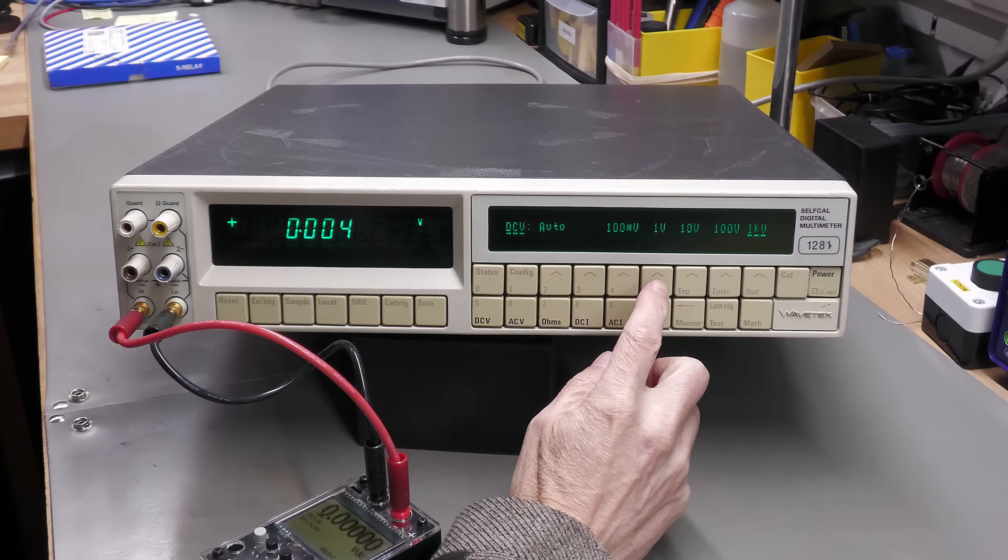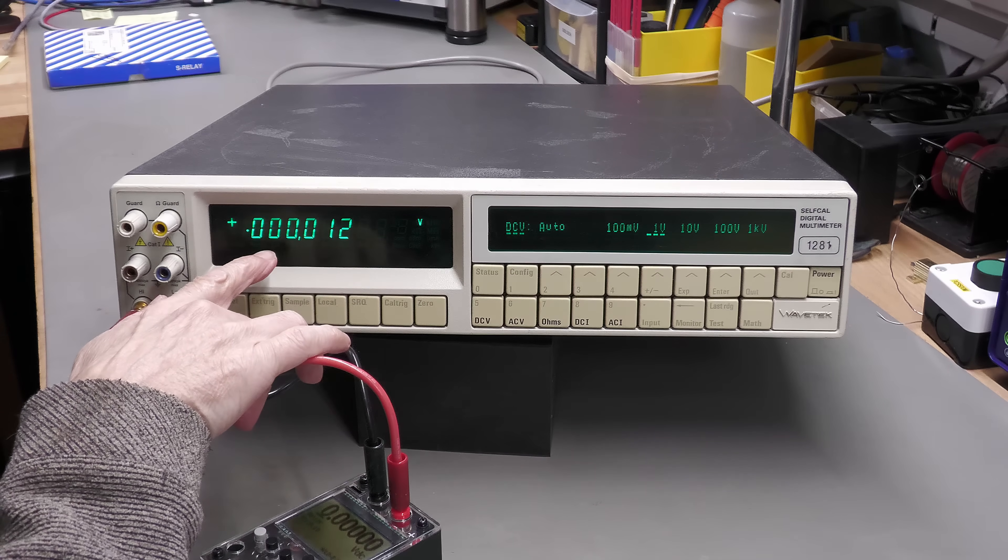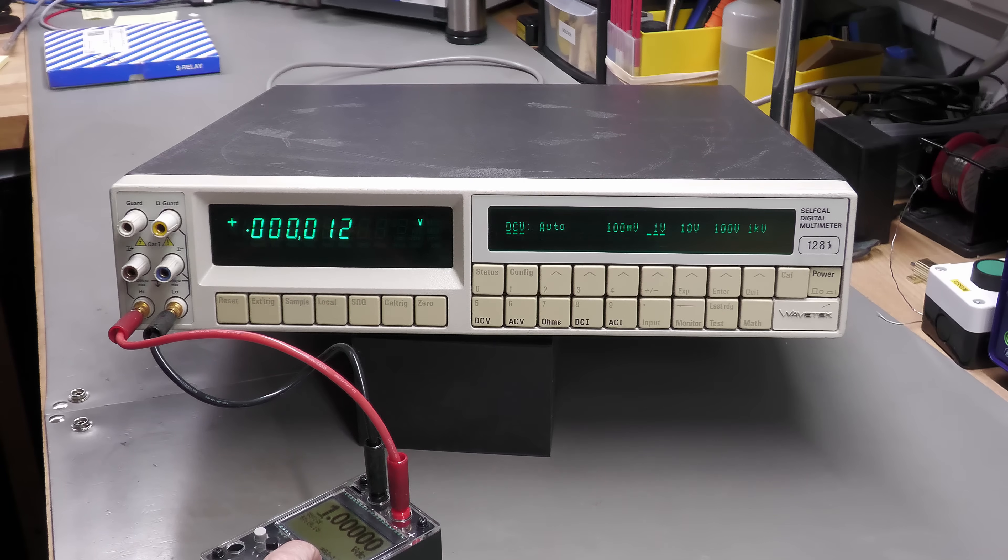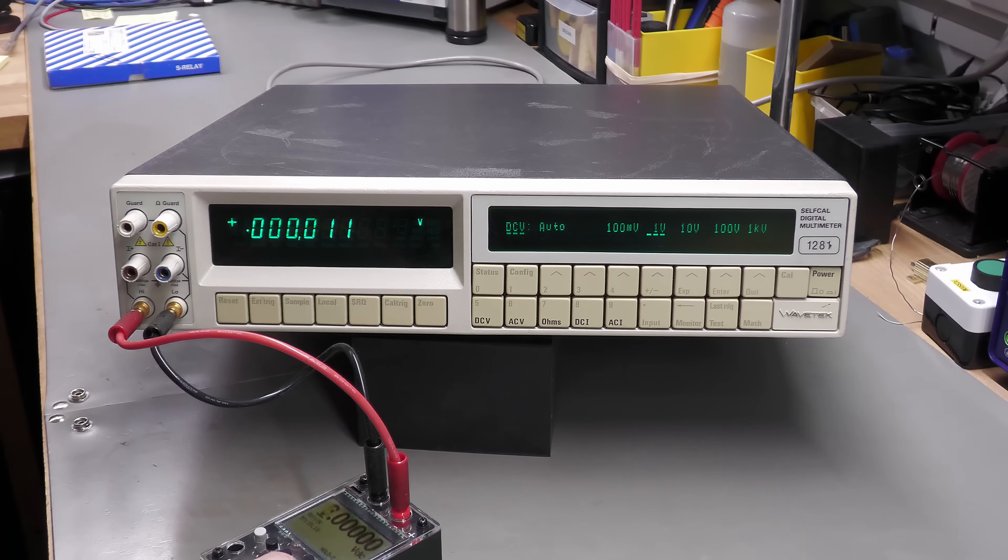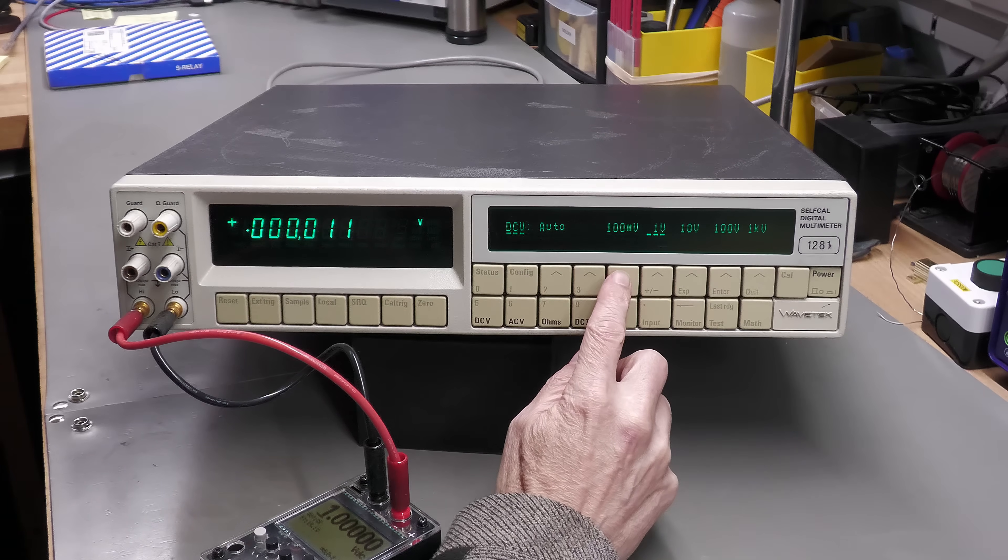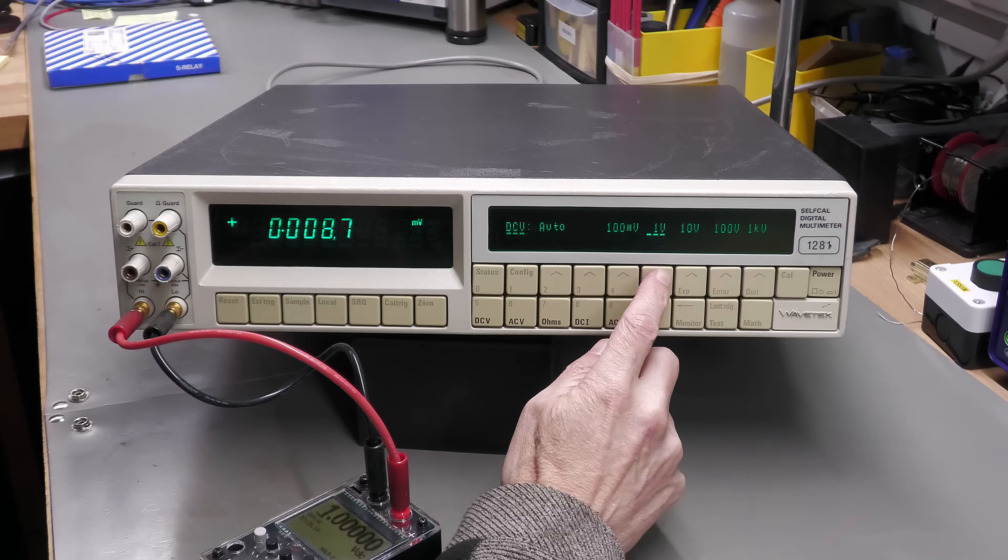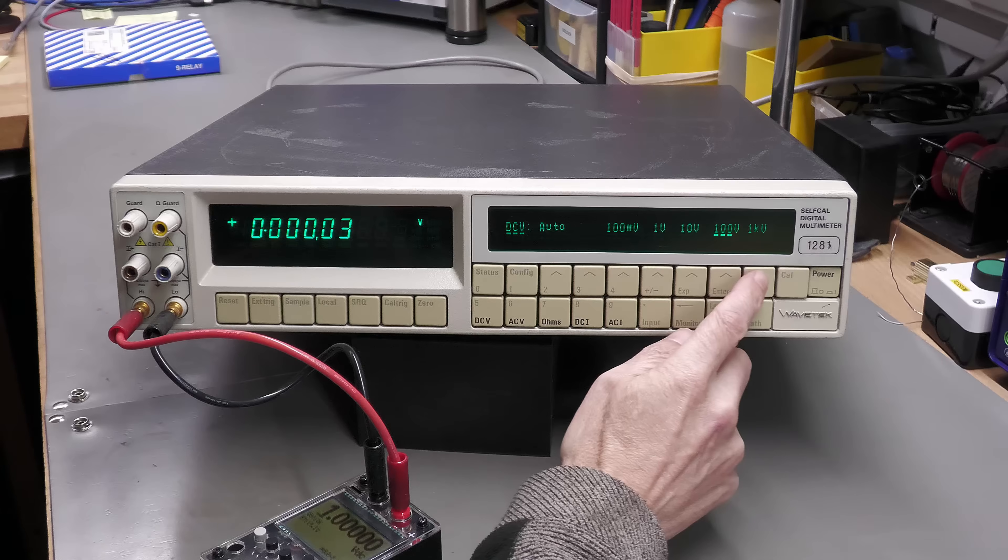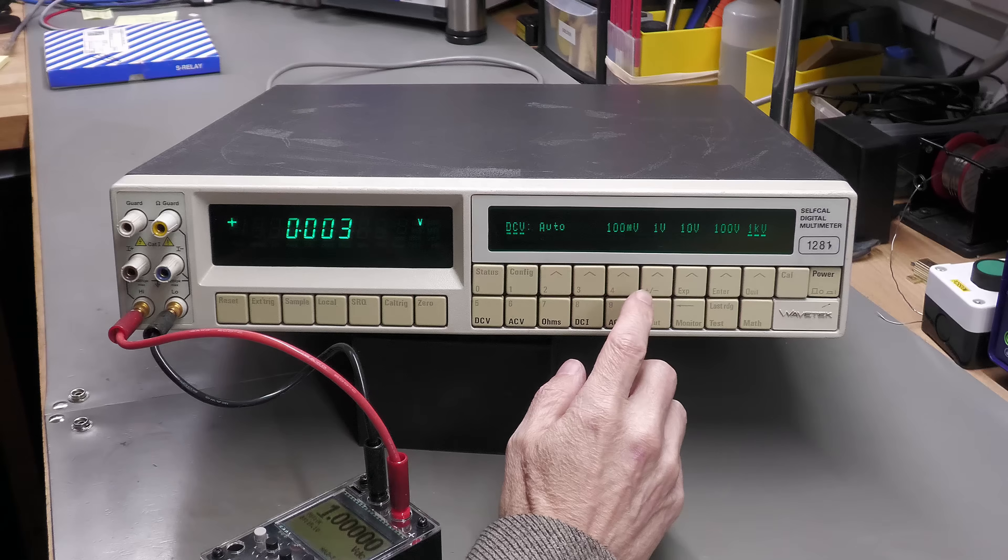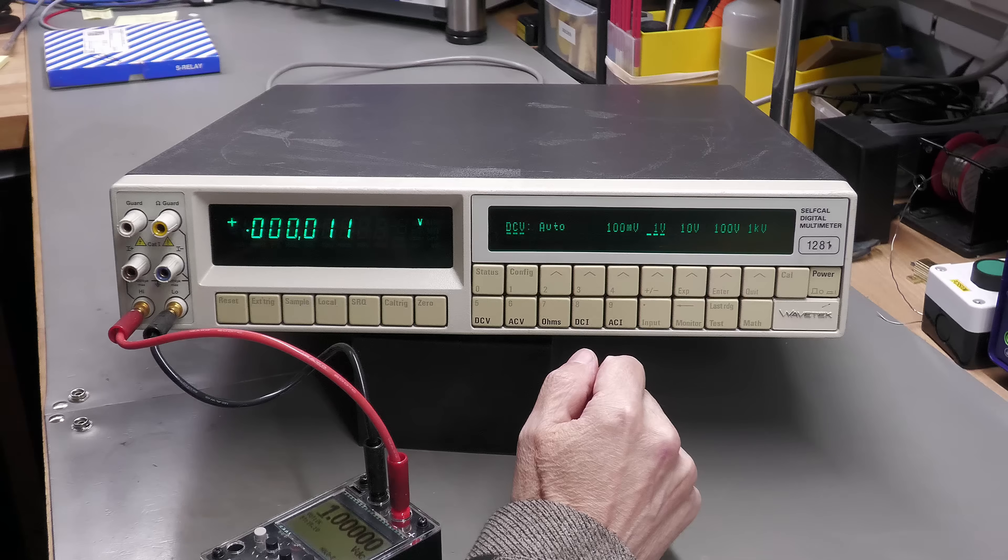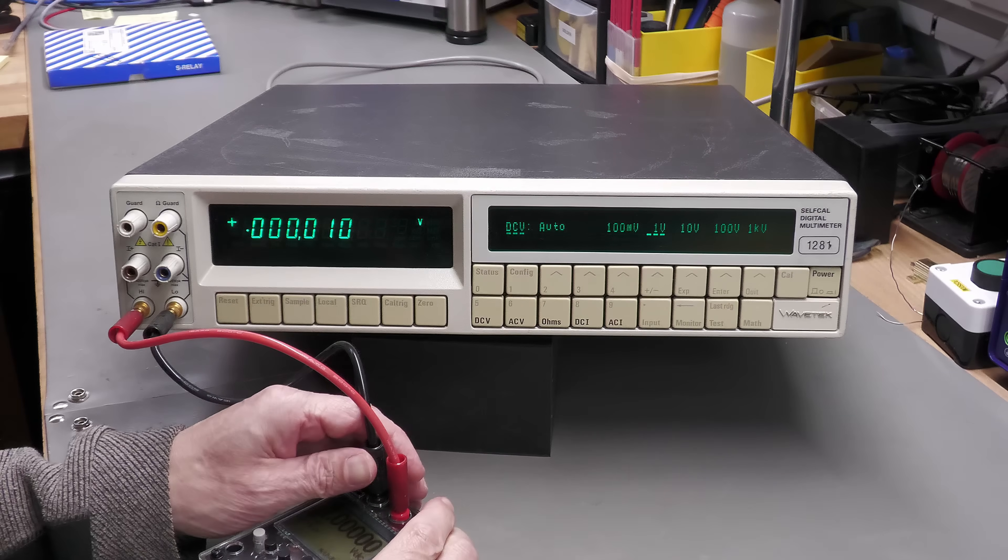Let's go on to the one volt range and it did change in the display here. Let me put in one volt. It's not changing all the way up to 10 volts, nothing at all. I'll back down to one volt. I should over scale the millivolt 100 millivolt range. It looks like I've got zero volts. It thinks there's zero volts coming in to the input circuitry. So yes there's a definite problem with the unit.